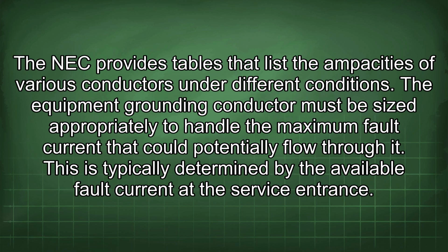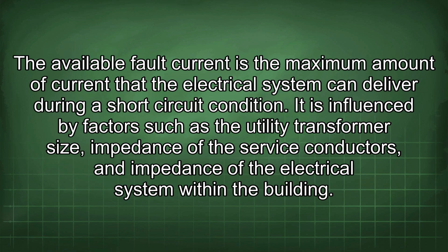The NEC provides tables that list the ampacities of various conductors under different conditions. The equipment grounding conductor must be sized appropriately to handle the maximum fault current that could potentially flow through it. This is typically determined by the available fault current at the service entrance. The available fault current is the maximum amount of current that the electrical system can deliver during a short circuit condition. It is influenced by factors such as the utility transformer size, impedance of the service conductors, and impedance of the electrical system within the building.